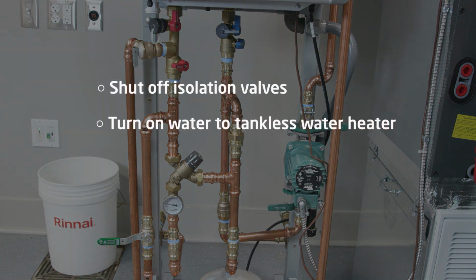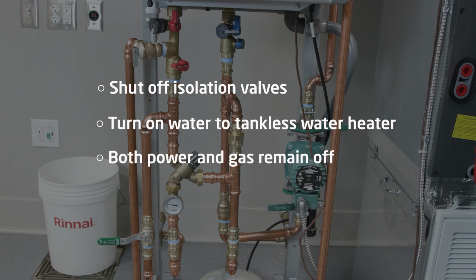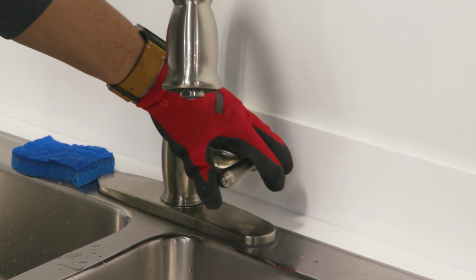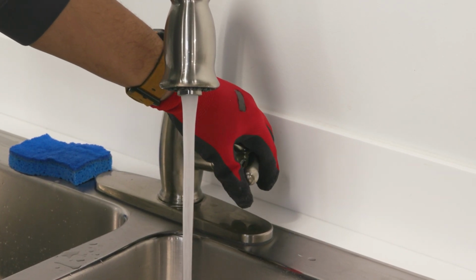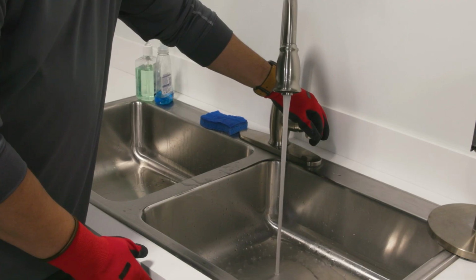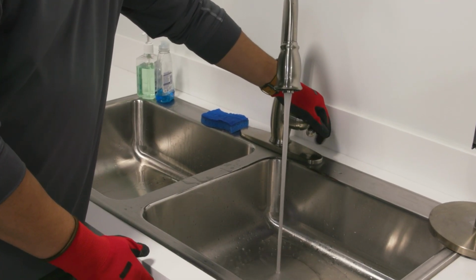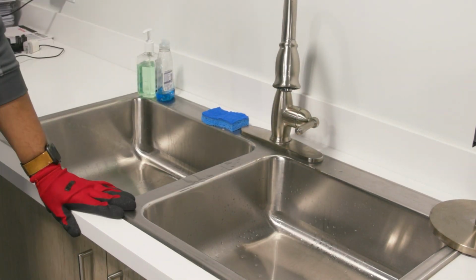Shut off the isolation valves and turn on the water supply to the tankless water heater. Both the power and gas should remain off at this point. Open the pressure relief valve to fill the tankless water heater. Stop when the water is discharged. Bleed air from the system by opening the hot water faucet that is the furthest from the tankless water heater. Close the faucet when the water starts discharging from it.